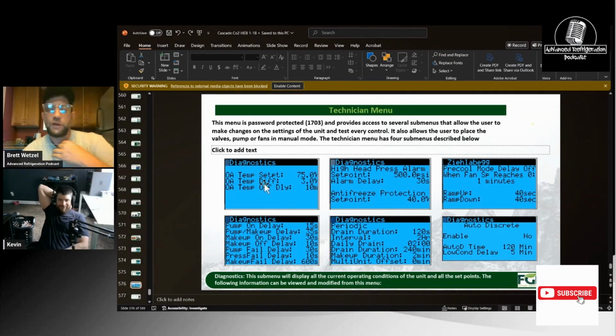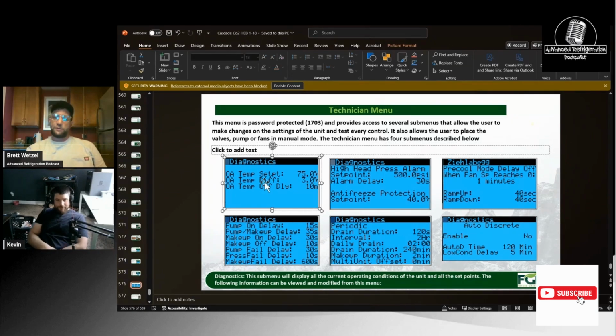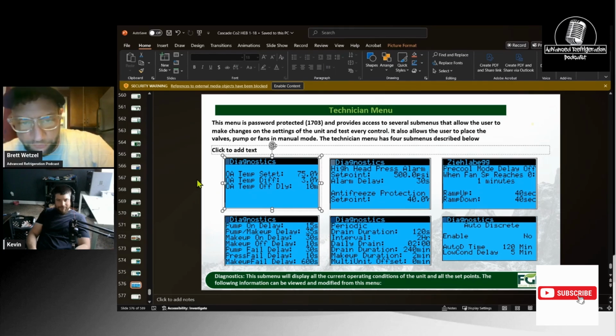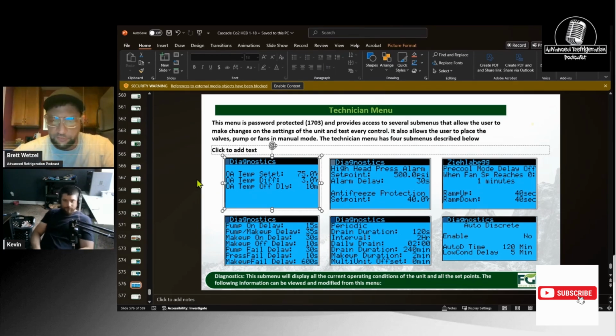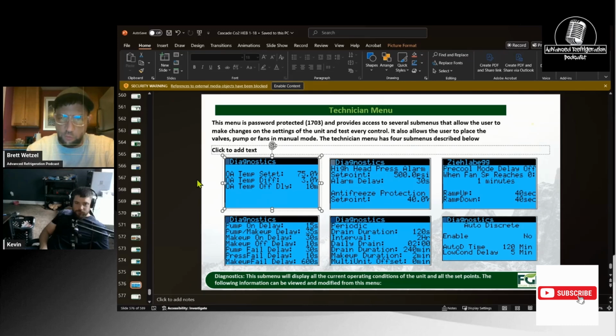Anyway, right here we have the analog outdoor air temperature, and there's our temp differential. This one sets for 75, 3-degree diff. So basically once it's below 72 degrees, but it has to be below 72 for 10 minutes. Not every single one utilizes the next thing over here with the high head pressure alarm. That's only if you're using some kind of pressure control. This is the pre-cool mode delay off when it reaches set point. So I have to ramp up, ramp down. I think this has to do with this part of the menu here.